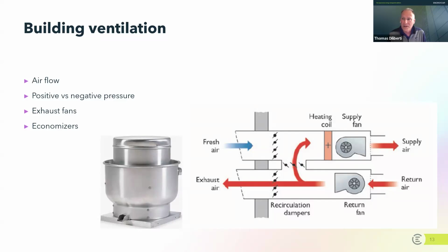So let me turn this around and say, how about we're putting less air in than is being taken out? In this situation, a building would be negatively pressured. What that means is there's more pressure outside the building than inside the building, so air will be pushed into the building through crevices, under doors, or around windows, and you'll get air intrusion into the building. And many times the air that's pushing into the building is air you don't want to come in. It's either humid, hot, or cold. It doesn't have the quality of air that you want.